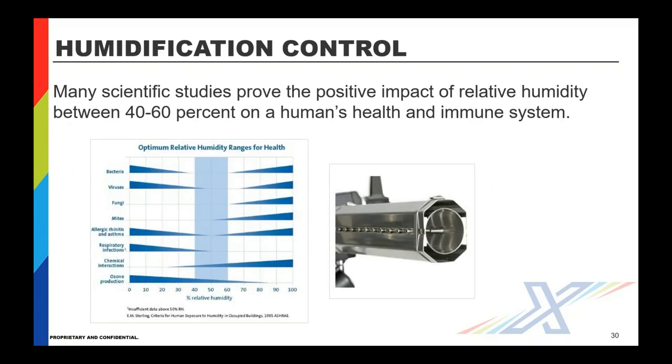There's a lot of evidence showing that humidity needs to be maintained between 40 to 60 percent relative humidity — perfectly in ASHRAE's human comfort zone. Bacteria, viruses, mold, and allergens can thrive in very dry climates as well as very humid climates. Beyond 60% RH there are problems, but also on the dry side: a dry nasal passage makes it difficult to fend off any kind of airborne infectious disease. So being in a humidity-controlled environment between 40 to 60 percent is beneficial from an infection control standpoint.